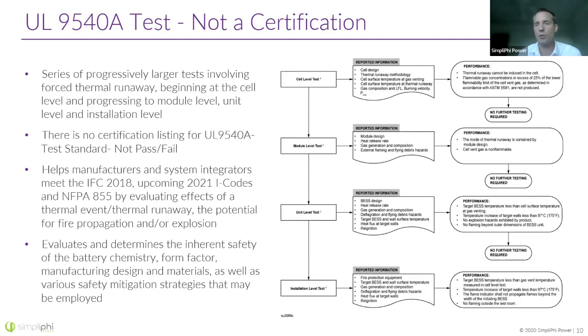The module also goes through similar testing. We evaluate the module design, make sure the BMS is safe, look at the heat release rate when the module is heated, examine external flaming, and assess the risk of deflagration—explosion—and exposure. If all these tests on the module are okay, no further testing is required and we proceed to the next stage.